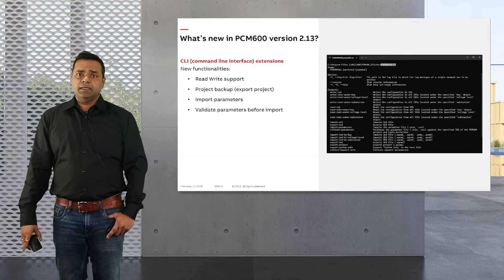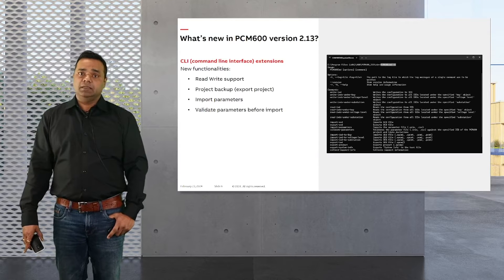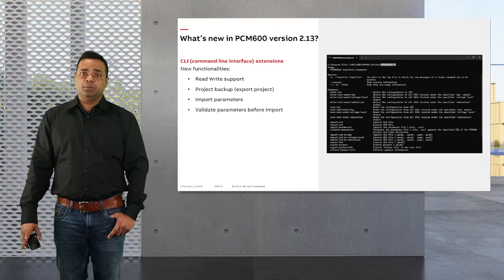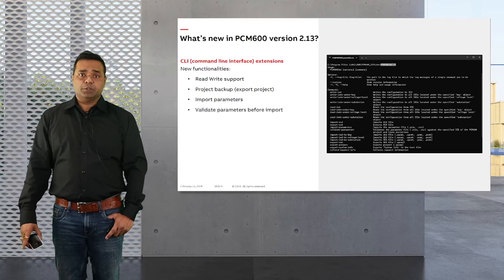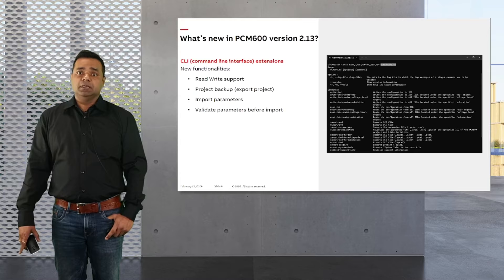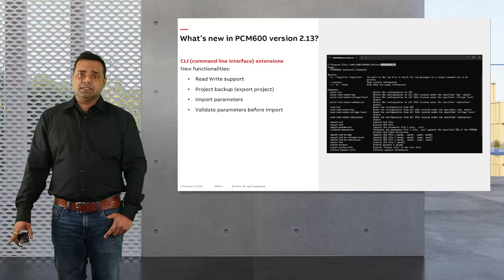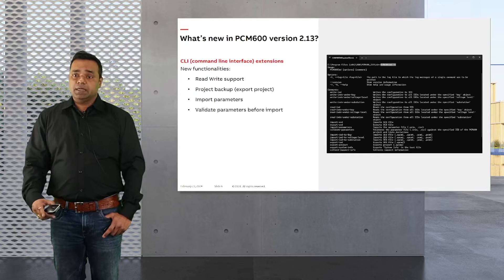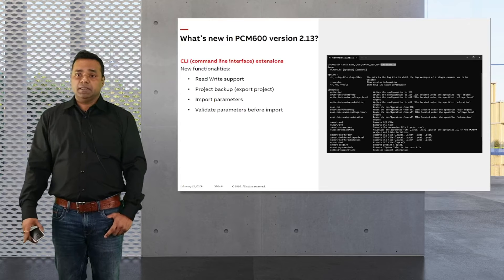Command line interface as a functionality has been available in PCM 600 for a while. Now with PCM 600 2.13, a few more capabilities are introduced — for example, read/write support, project backup, validate and import parameters. The command line interface is quite useful in that commands can be listed in a batch file and then executed.